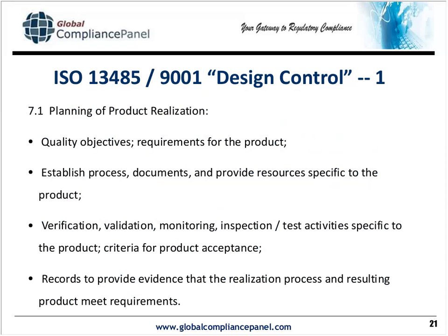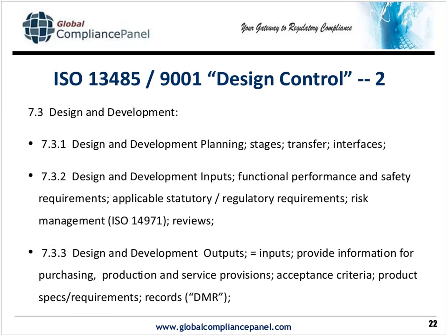Now, ISO 13485 does require design control. This is under 7.1, planning of product realization. And so much of the same is required, except as I mentioned, the resulting documentation under the ISO 13485 medical device directive expectation is that it's a snapshot in time, although they are looking at changing that to having more development history in it, to make it more like a design history file. But as I mentioned earlier, that's a key issue, a key difference.